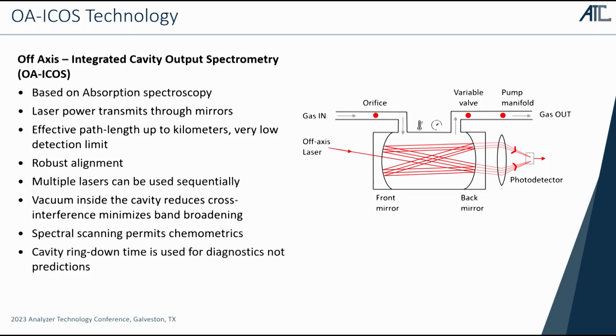The off-axis design makes it very simple to integrate more than one laser and then pulse between the 2. So if you can measure, in one example, HCl and HF with one laser, you can slap in a second laser and measure ammonia. It has that capability. The other really nice thing about this parabolic optical arrangement is it keeps the light aligned, so to speak. So it brings some rigidness to a slightly vibrational area, what you would expect to find in a process environment. Makes it a very robust alignment.